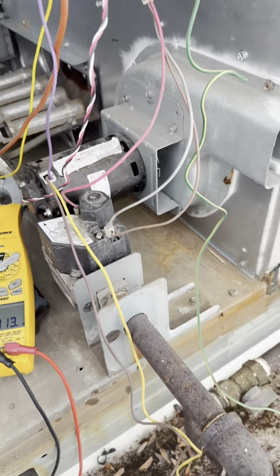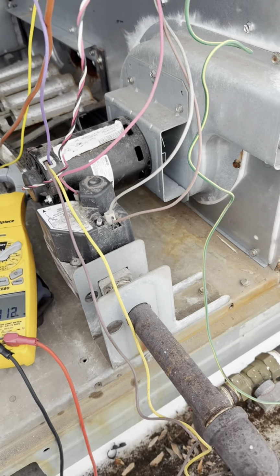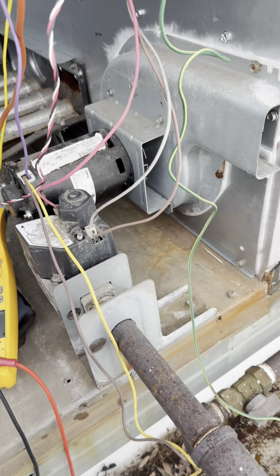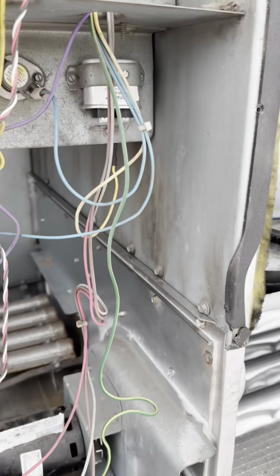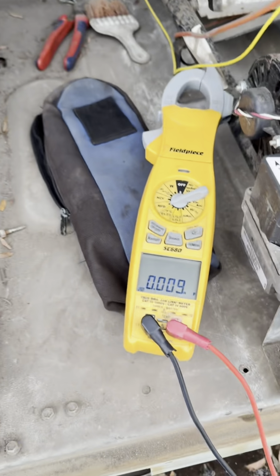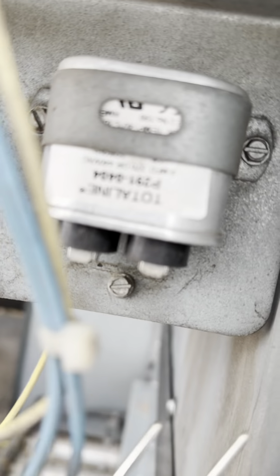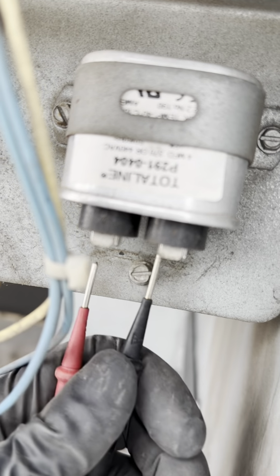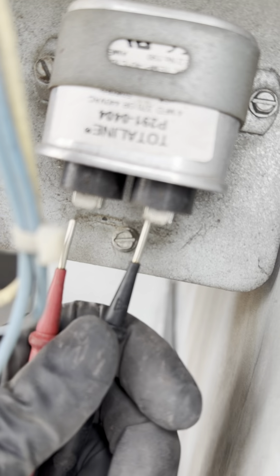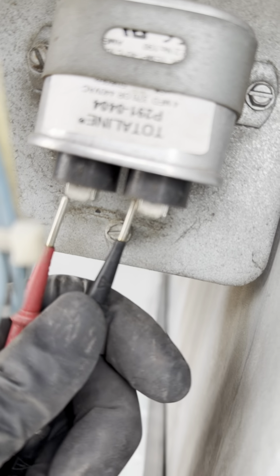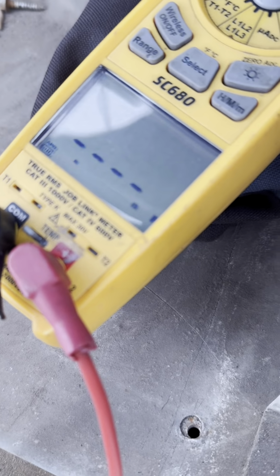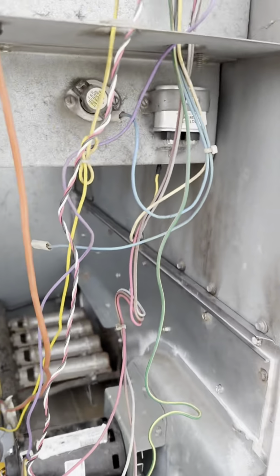All right, because we didn't replace the inducer motor because it was working, we're going to go ahead and check the capacitor on the inducer motor, make sure that it's okay. We don't want any callback. Set the meter on microfarad. This capacitor should be reading 4 microfarads. And we are reading the 4 microfarad. So I'm going to plug that in.